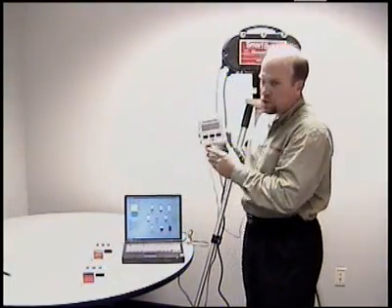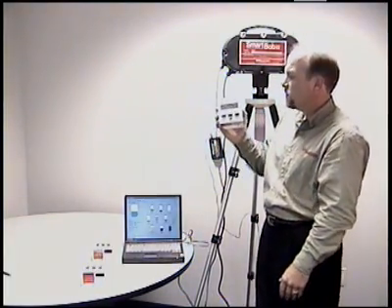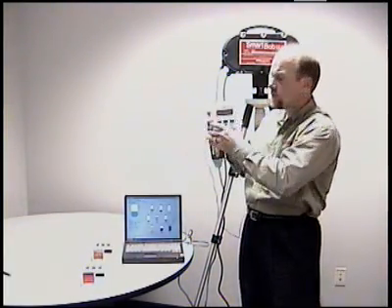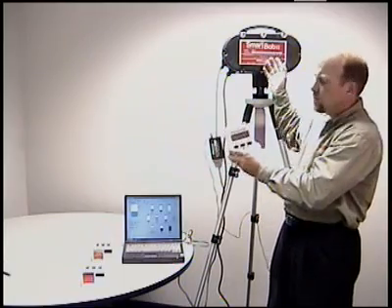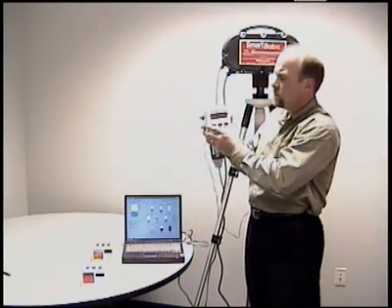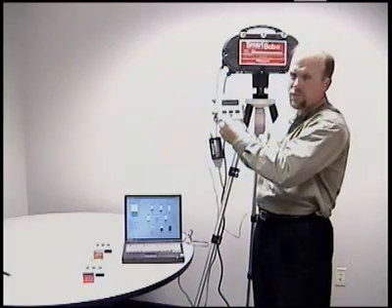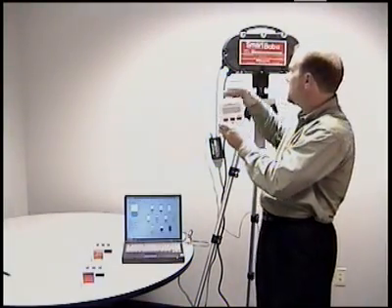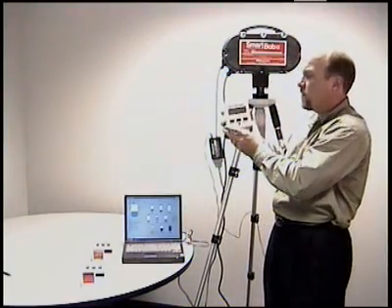We have an RSU, which is a remote start unit, which is the interface between a PLC or DCS and the SmartBOB2 remote. And what this will do is you get a dry contact closure in from the PLC or DCS to initiate the measurement on the SmartBOB2 remote.